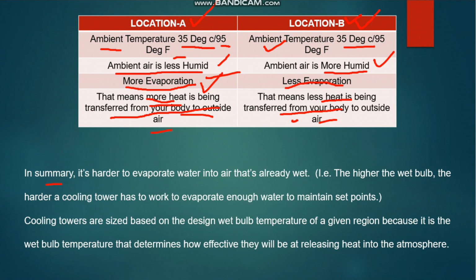So in summary, it is harder to evaporate water into air that is already wet. That means the higher the wet bulb, the harder a cooling tower has to work to evaporate enough water to maintain the set point in the system. So that's the main reason a cooling tower works based on the concept of evaporation, or evaporative cooling. It will transfer the heat load through the evaporation.